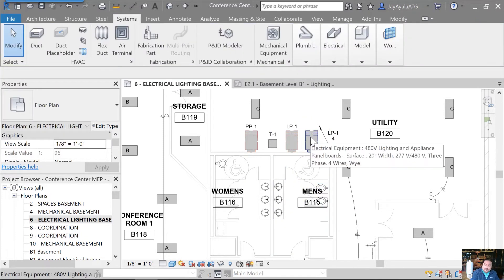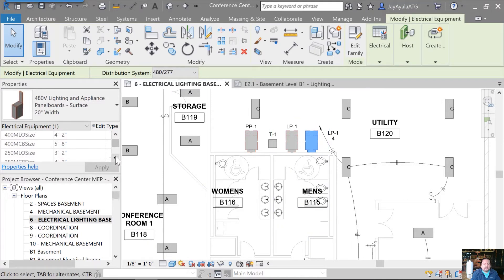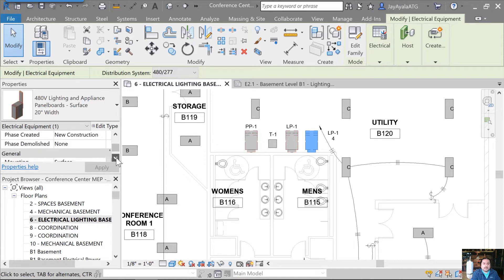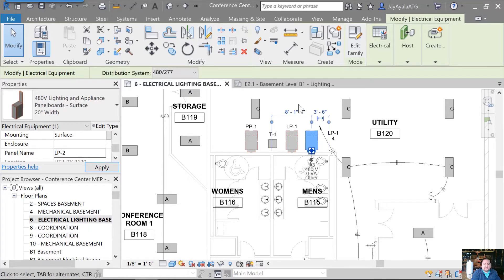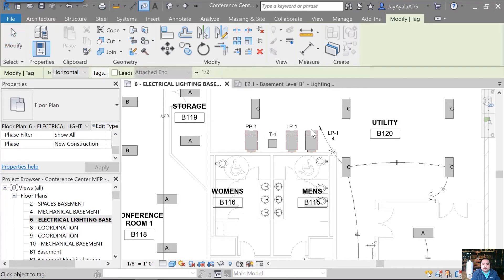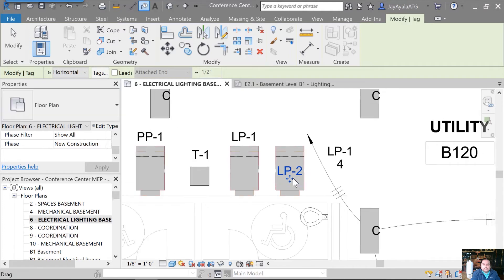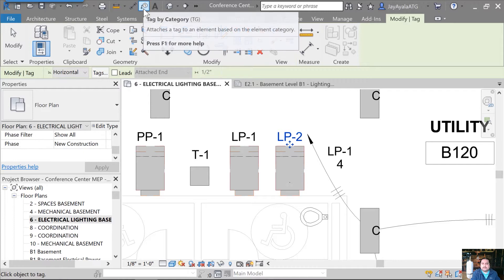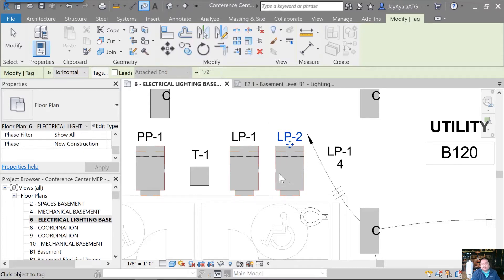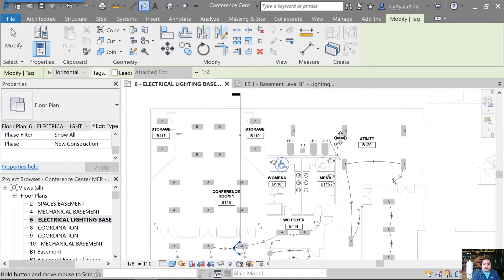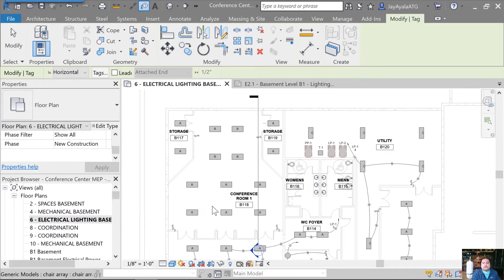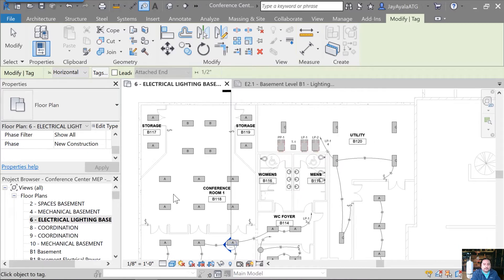Next, once it's placed, we can go ahead and select it and we can look at the properties based off of what we're looking at here. Specifically, I'm looking for the panel name. I'll just go ahead and continue clicking further down the list here until I get to the panel name and I'll fill that in. As you can see here, it's not filled in. I'll just put, in keeping with the naming convention there, LP-2, that panel is now named. I can do the same for that power panel, but let's document this, right? The whole thing about this is that it's supposed to be easy documentation. So what I just did is I added a tag based on its category. And because this tag is reading the panel name, it automatically brings that in. I don't have to type it in again. Next, what we'll do is we will add all the lighting in conference room one, along with the corresponding storage rooms to panel LP-2.